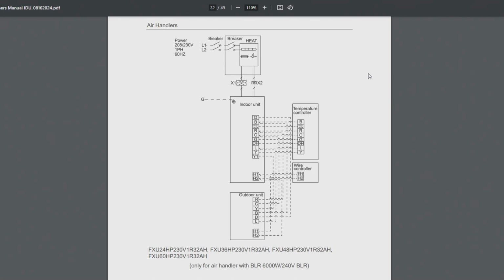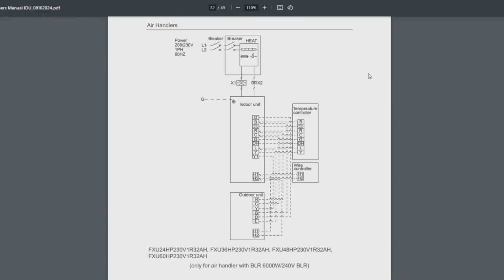So in this, I know what you guys may be thinking: what's this got to do with using another manufacturer's unit? Well, that's why I pulled up the wiring diagram here. If you look at the thermostat, you've got a Y connection from your thermostat that goes to Y on the indoor unit. And then from the indoor unit, Y1 goes to the outdoor unit Y. The reason for that is there's a relay in that board. So once it goes into alarm, it breaks the connection between Y and Y1 and drops the compressor immediately.